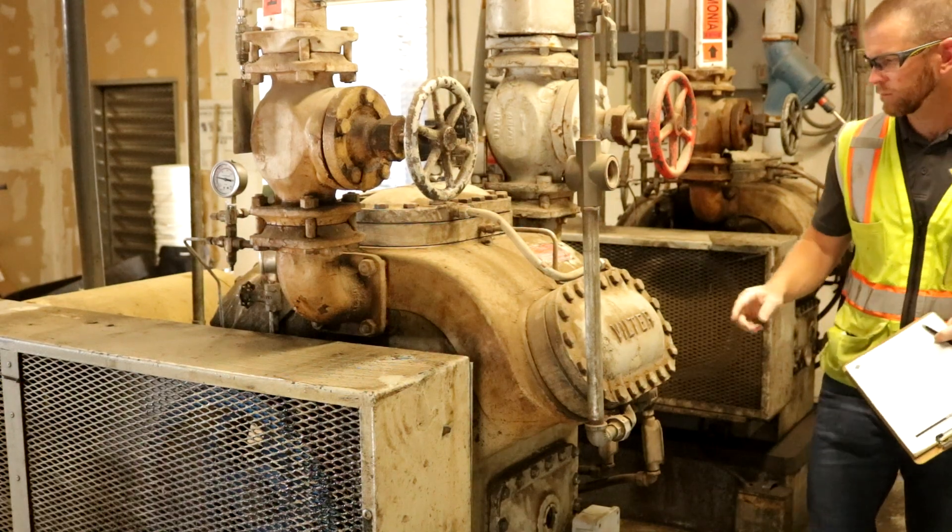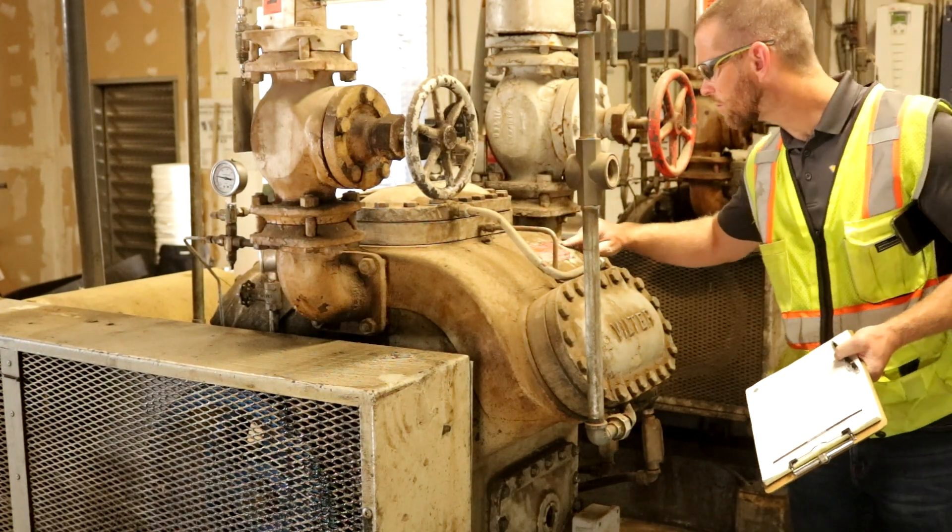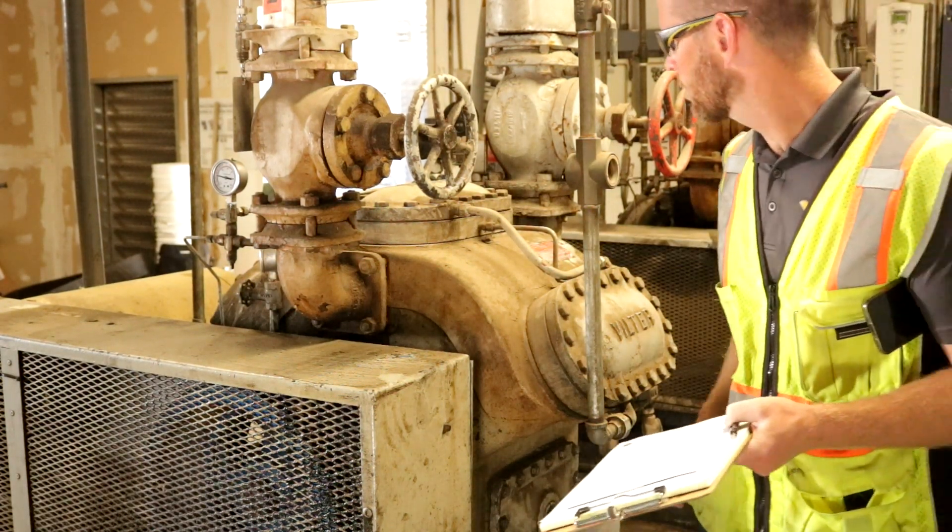Engineers and plant operators achieve this in part by utilizing capacity control in compressors. In reciprocating compressors, capacity control is accomplished by cylinder unloading.